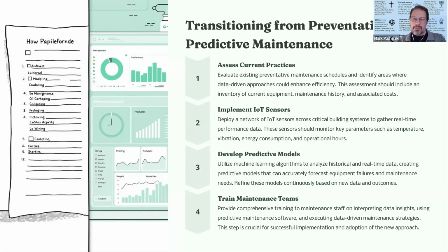So predictive maintenance, with that same filter change, I'll put what's called either a magnehelic or I'll measure a pressure drop across that filter. As the filter starts gaining dust and debris, it's harder for that air to get through that filter. So there's a bigger pressure drop from the fan pulling the air through the filter on one side of the filter to the pressure on the front side where it's being pulled in from the outside. That pressure drop can be measured. And then that can send me a signal to say it's time to change your filters.